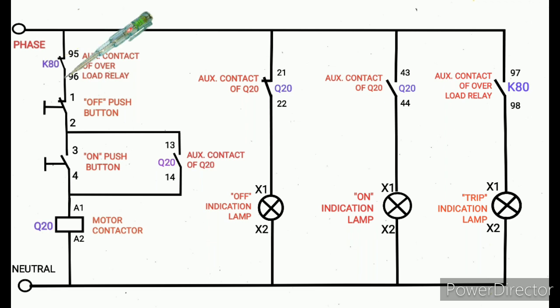Next, that NC, after that NC, the 96 terminal number 96. If the 96 tester glows, that NC contact is okay, means that auxiliary contact of overload relay NC is good.